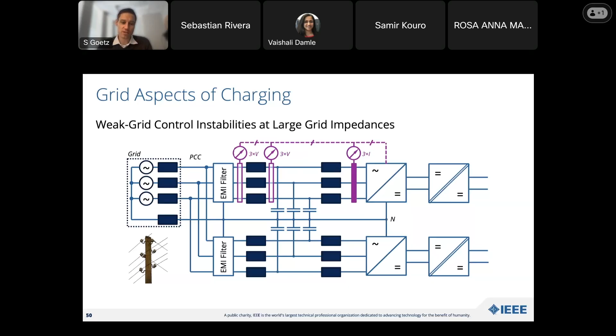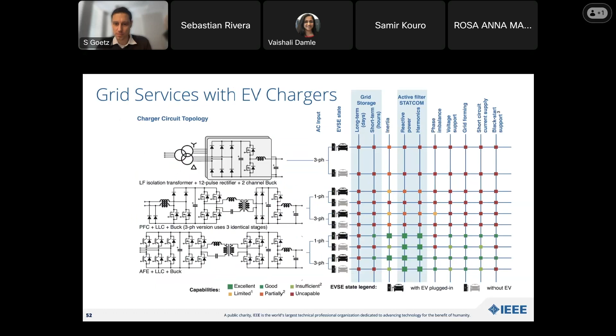The grid is in many places not very inductive. If you have underground cables, weak grids are usually mostly resistive, and weak grids are the most important application for voltage support. Overhead lines, long overhead lines which are in more rural areas, can have enough inductance for that method to work.